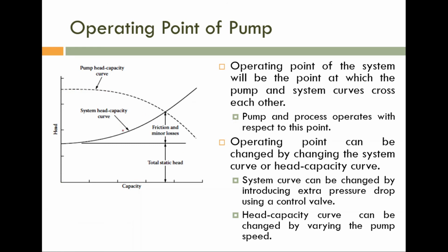So here we considered only the friction in the pipeline or the difference P1, or the boiler pressure, etc. If you are using a control valve, what will happen? Definitely a pressure drop will be there. Here this one is the input pressure and this one is the output pressure. So P1 minus P2 is definitely inversely proportional to the valve opening. If it is 100% opening, then P1 minus P2 will be small.